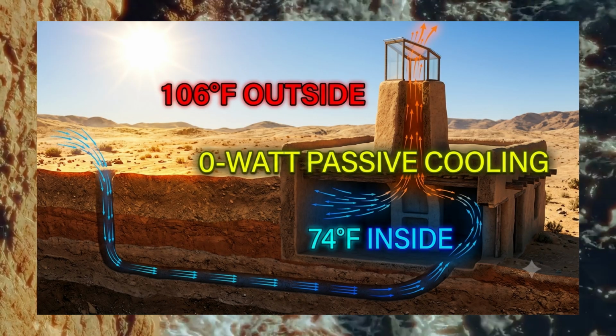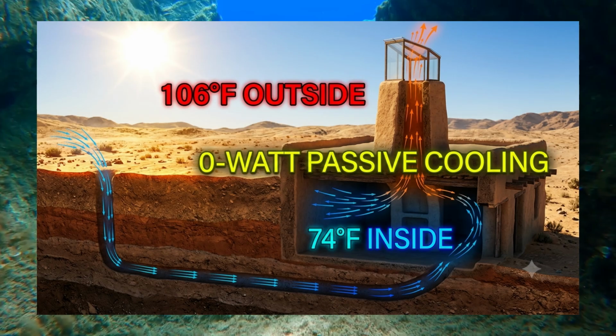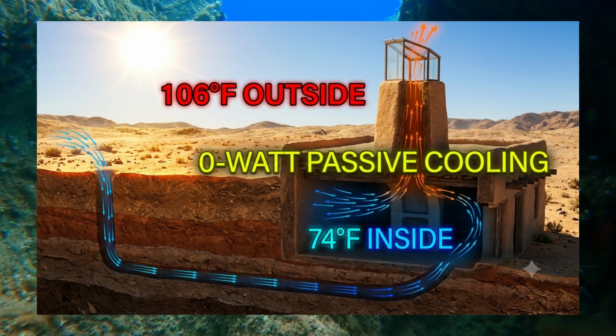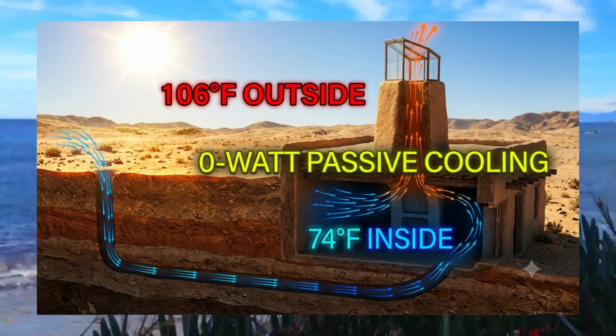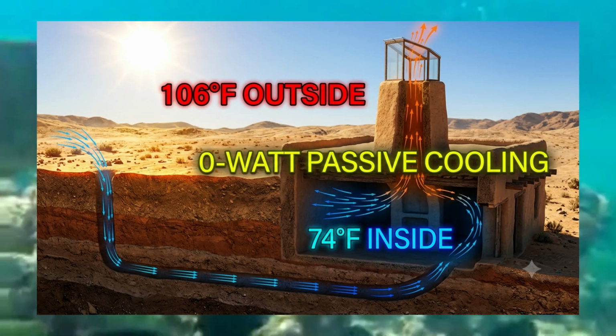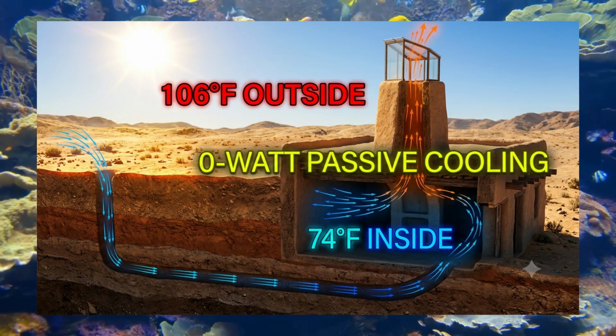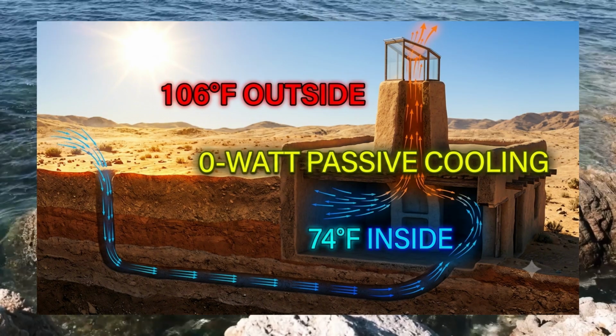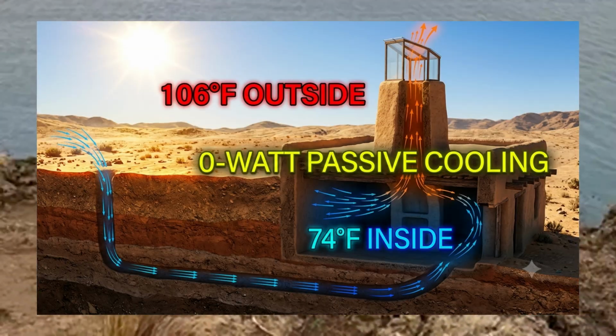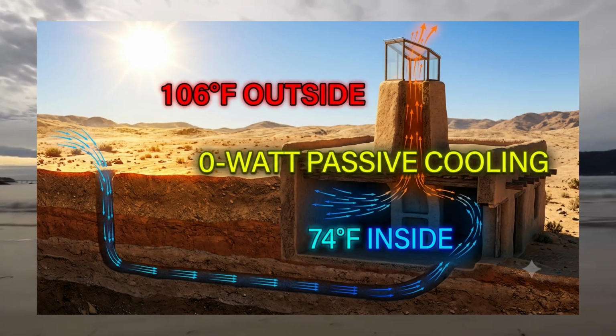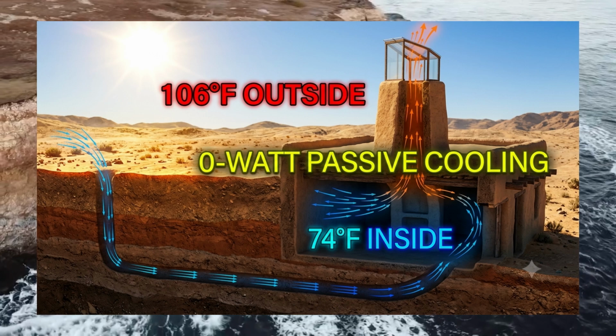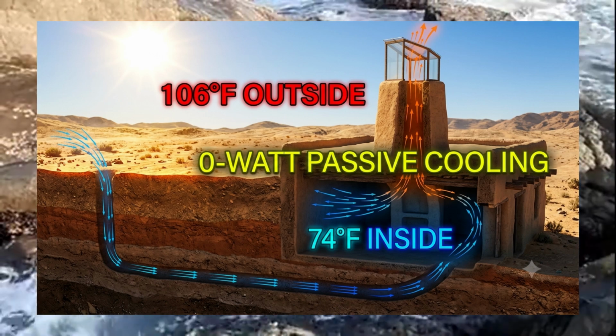At the far end of this subterranean pipe, we construct the low-level intake plenum. This is where fresh outdoor air enters the loop. It must be positioned in a heavily shaded area, ideally under the canopy of deep-rooted trees or on the northern, cool side of the building, and elevated at least 3 feet off the ground to prevent dust and ground-level debris from being sucked into the intake.